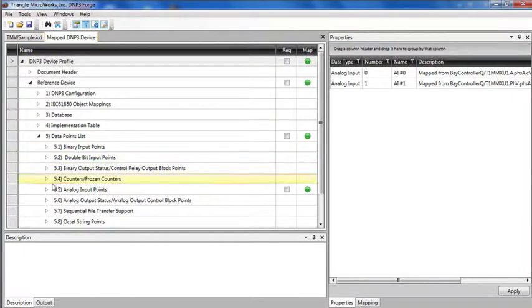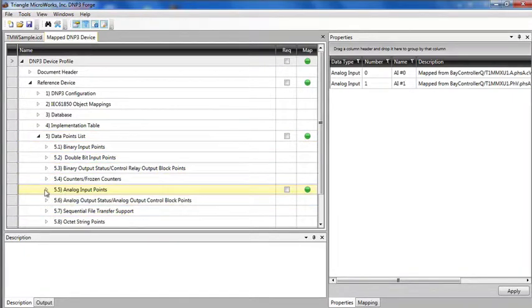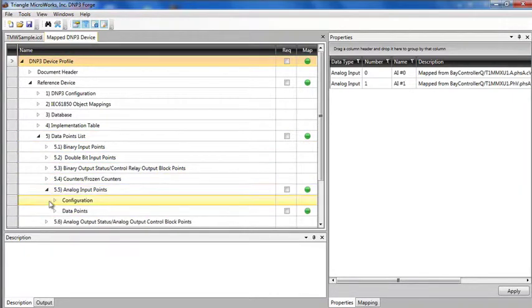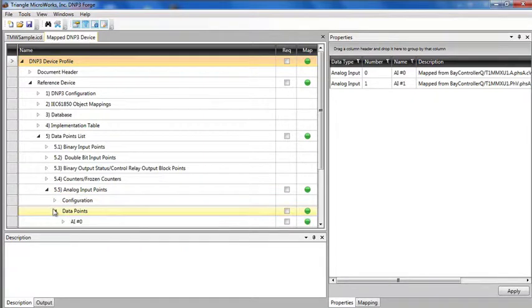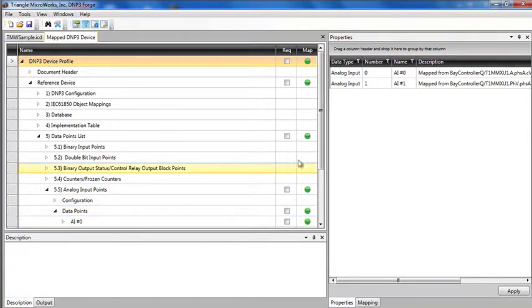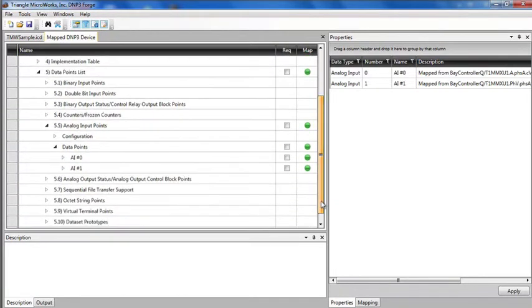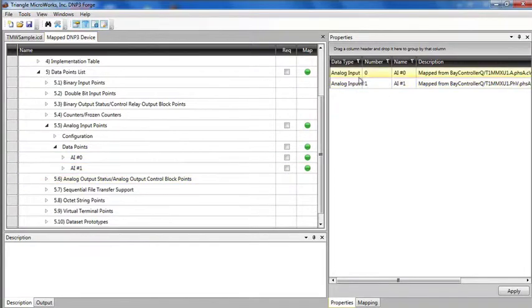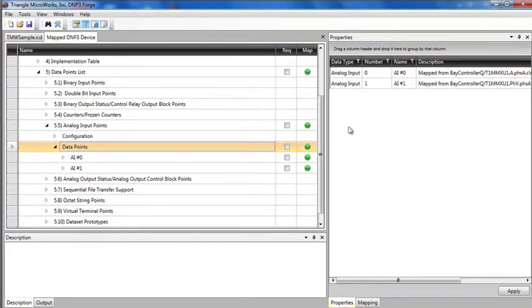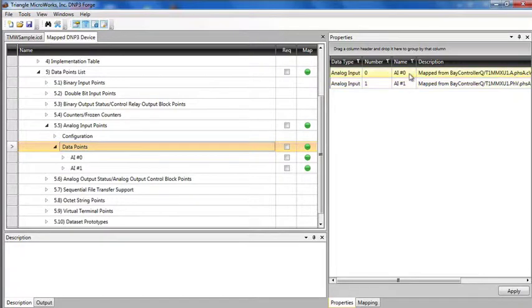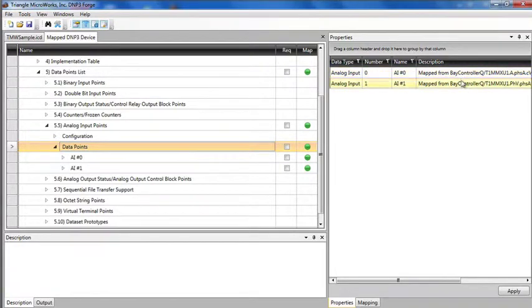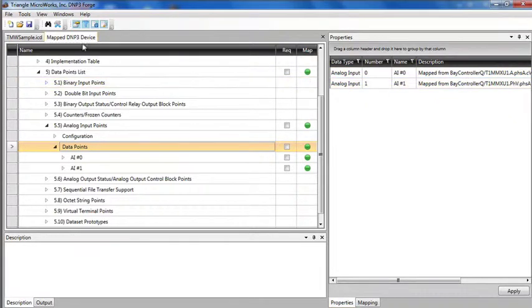I go look at my points list, look in my analog points. I'll see that it's created analog zero and analog one. Shows the points over here. Point name. And fills in the description what point it was mapped from in 61850. Now I'm going to save this file.